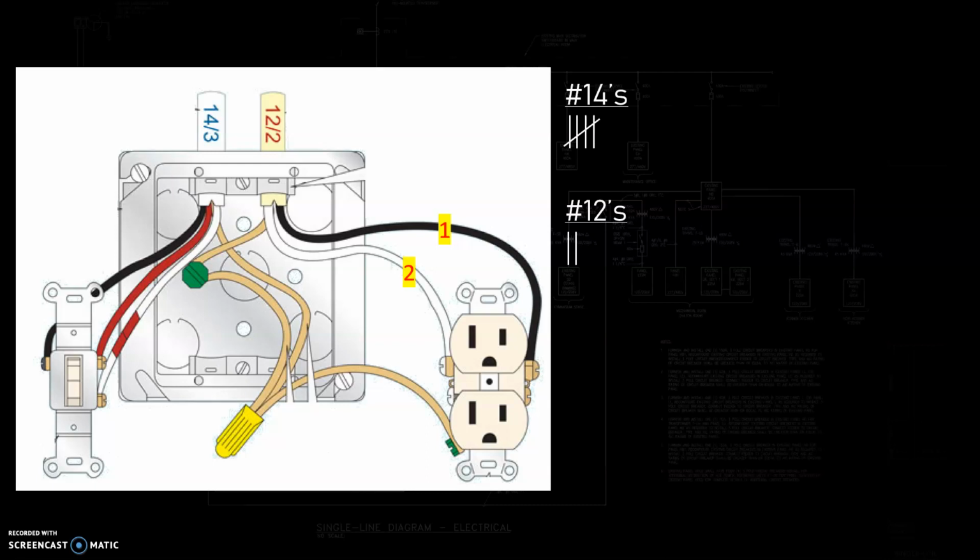Okay. Let's go ahead next and count the wires connected to that receptacle. Remember, a double volume based on the largest conductor connected to it, which is a 12. So we're going to count 3 and 4 for number 12s connected to the device. Then we do have to count our ground. In this case, the largest ground in the box is the 12. We're going to take a single volume based on our number 12. So that gives us 5 number 12s.